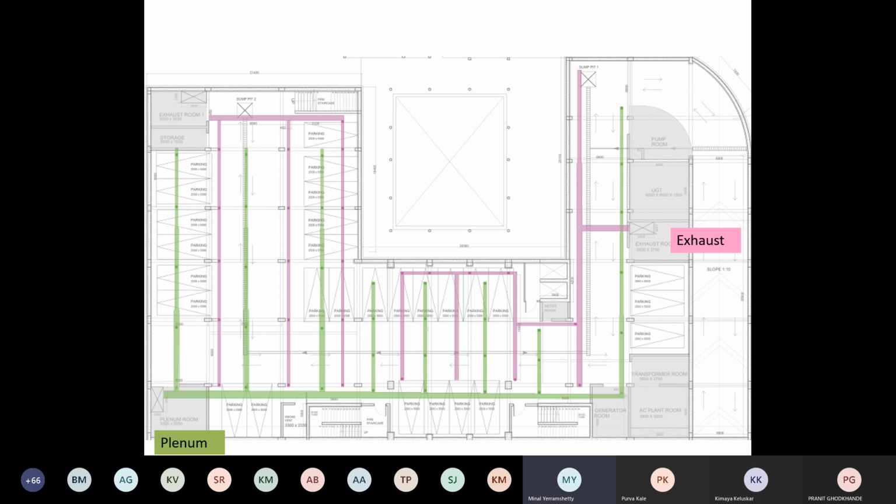Cross in this drawing. Okay. Now in this, those are the ones that I am talking about. If you see the top one near the sump on the extreme left, that is your exhaust room. Now, what she has planned, since hers was a C shape or U shape, whatever you call it, is that she will give more exhaust so that with a little bit of push of the air, the negative pressure will automatically pull the air in.